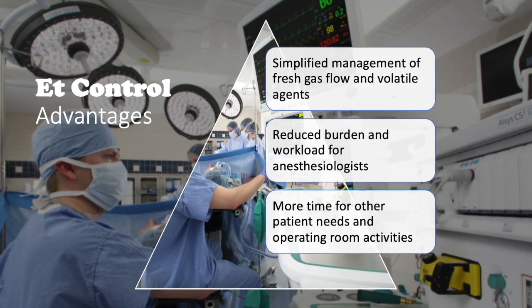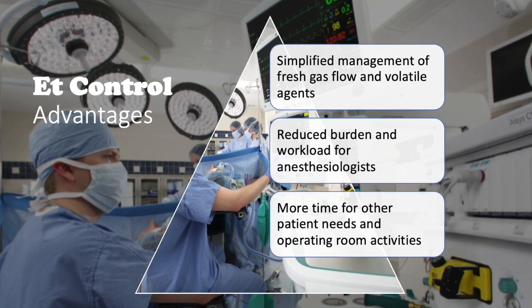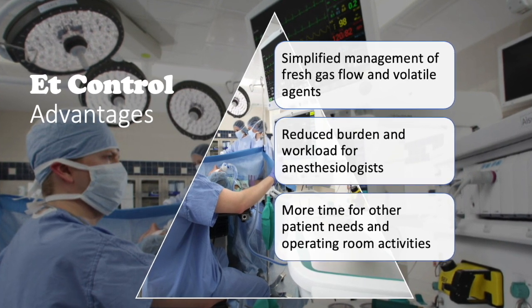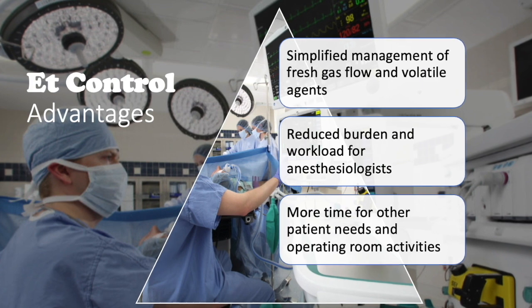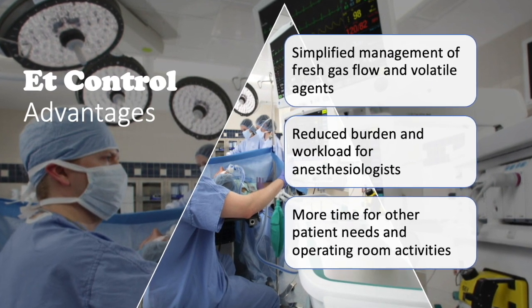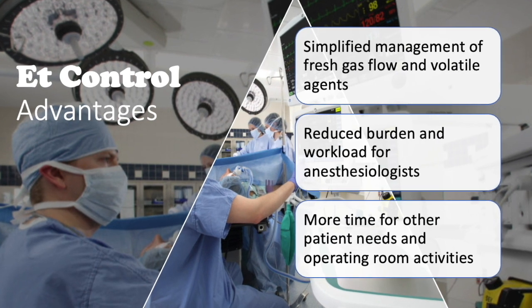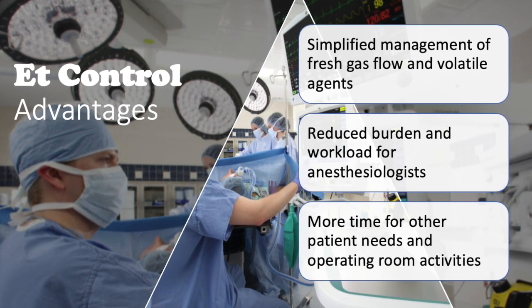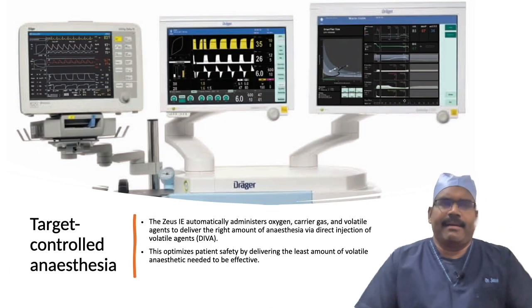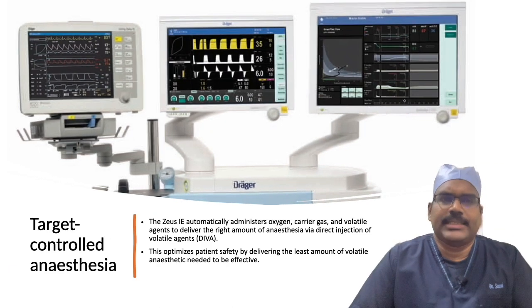These are the end tidal control advantages. This is a simplified management of fresh gas flow and volatile agents. There is reduced burden and workload for the anesthesiologist, and we can devote more time for other patient needs and operating room activities.